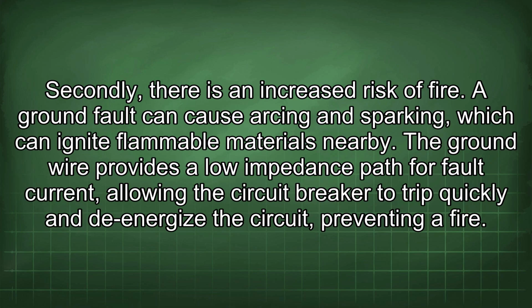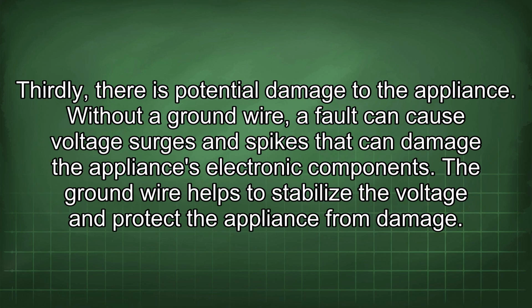Secondly, there is an increased risk of fire. A ground fault can cause arcing and sparking, which can ignite flammable materials nearby. The ground wire provides a low impedance path for fault current, allowing the circuit breaker to trip quickly and de-energize the circuit, preventing a fire. Thirdly, there is potential damage to the appliance. Without a ground wire, a fault can cause voltage surges and spikes that can damage the appliance's electronic components. The ground wire helps to stabilize the voltage and protect the appliance from damage.